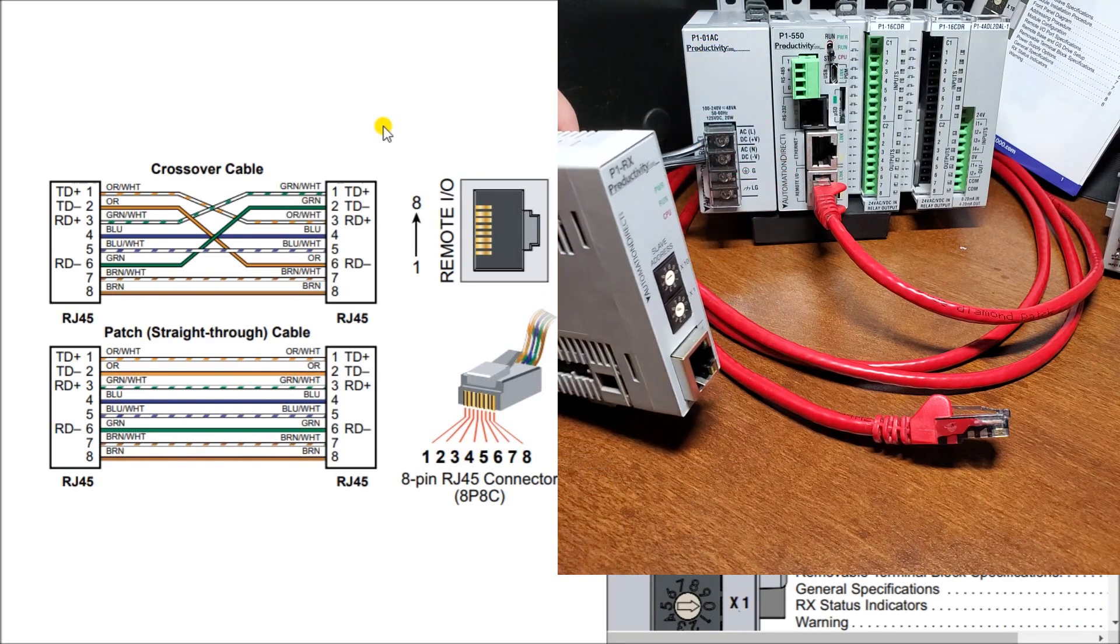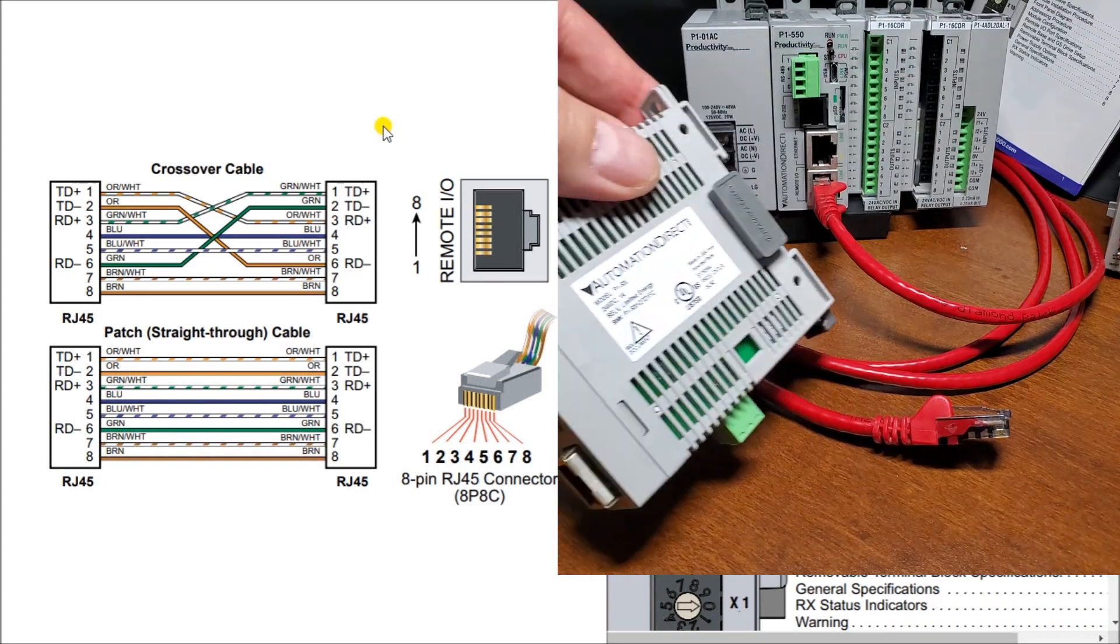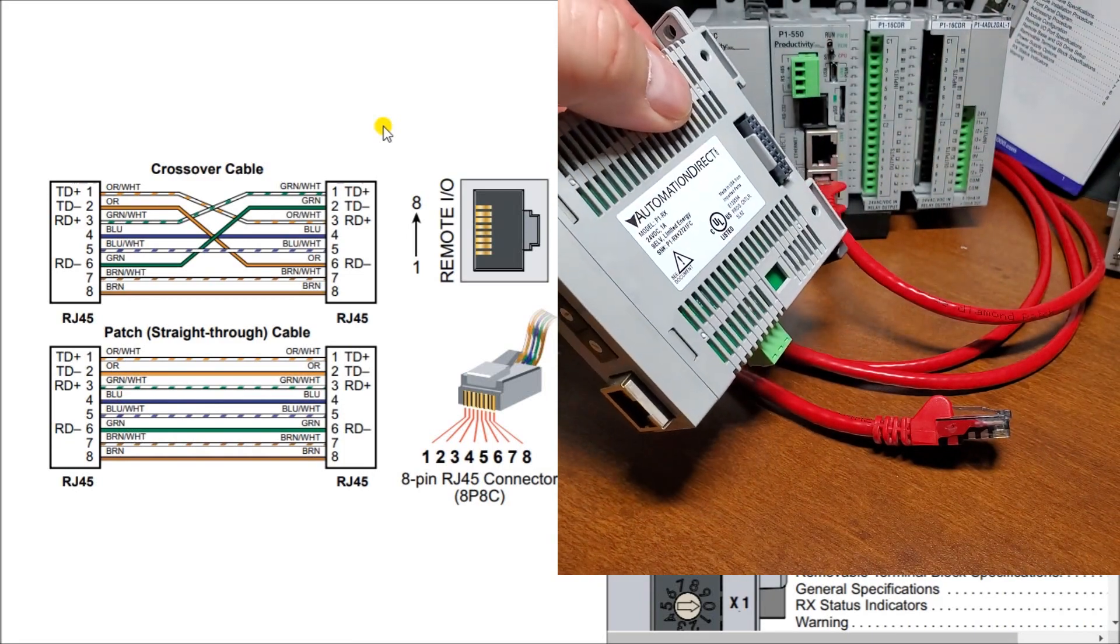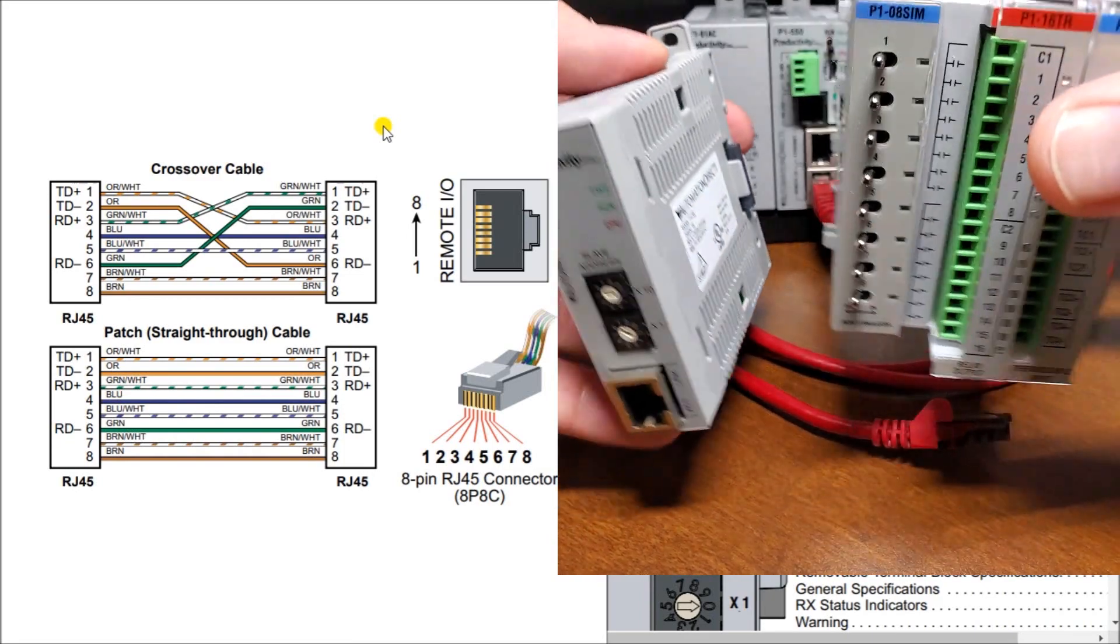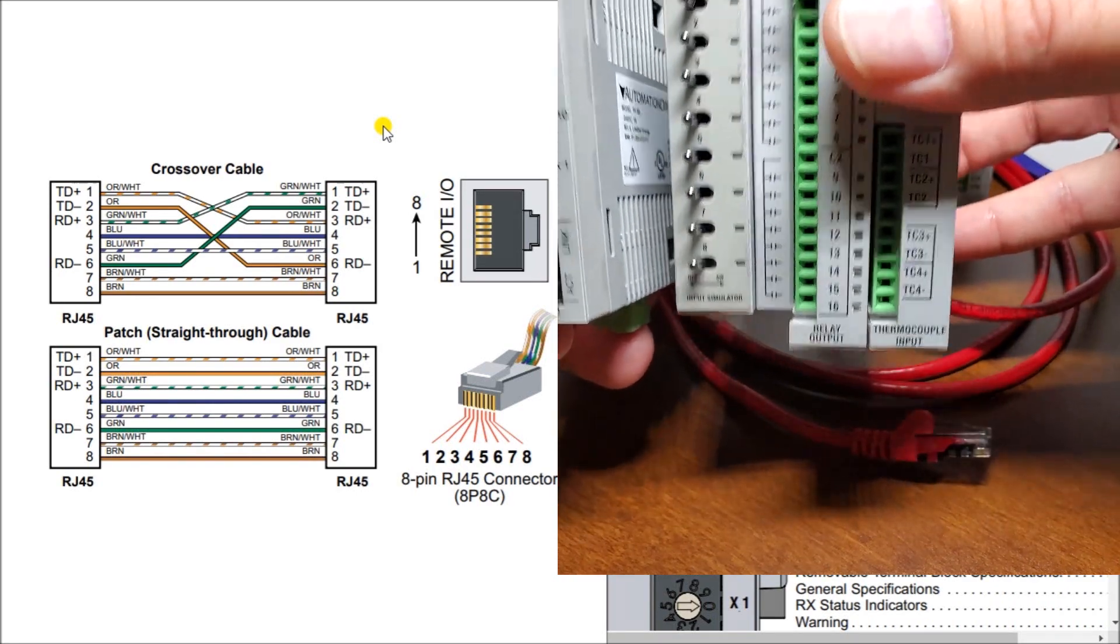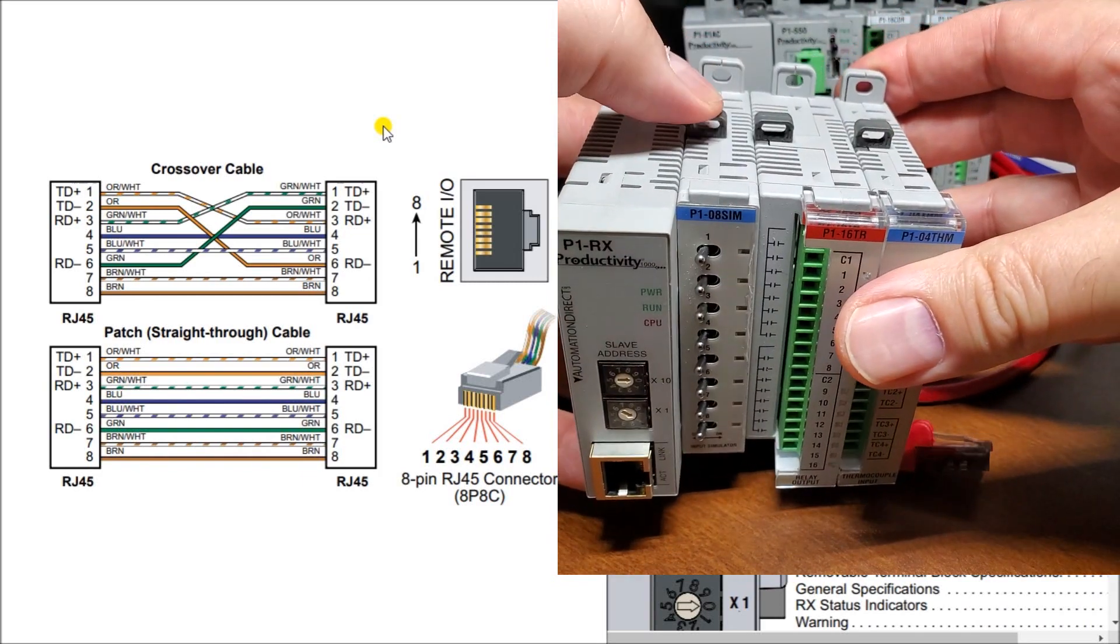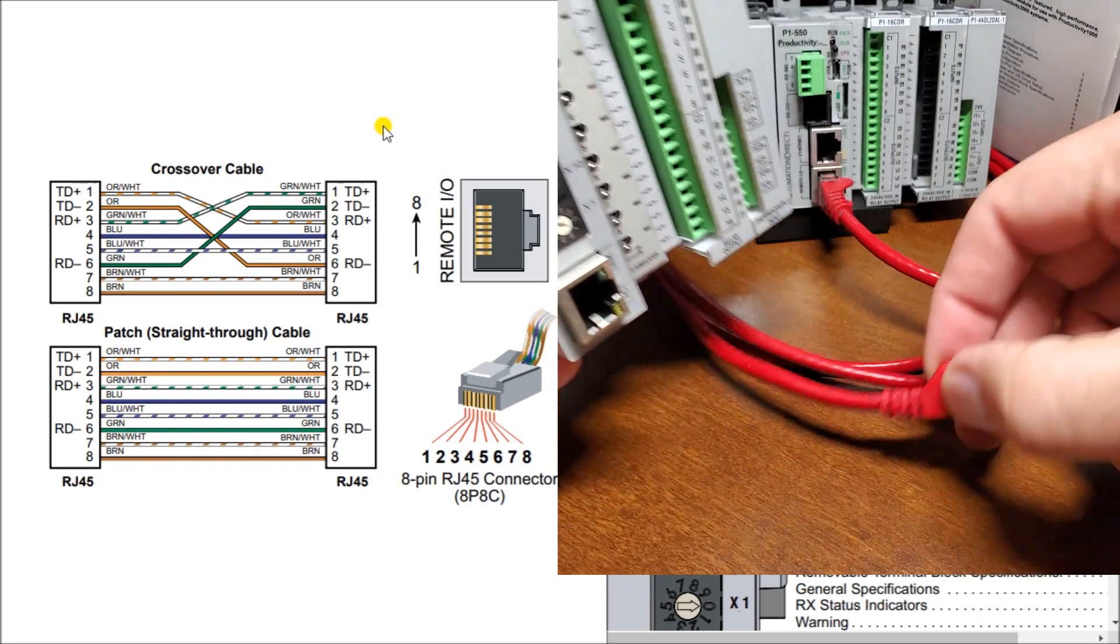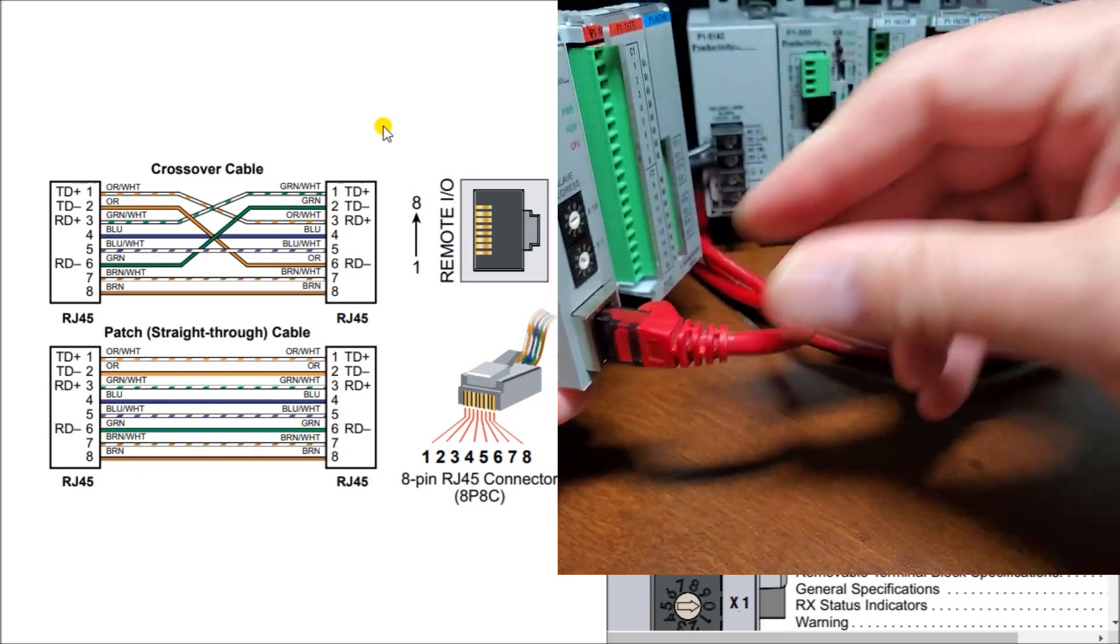So as you notice, like all the P1 series, we have a connector here on our bus. Take that off. We will take our list of I.O. cards that we're going to install, and they will actually snap together to this unit. Press down on the clip, and then it's ready to go. We'll take the bus connector, or the ethernet connection, and we'll just plug that in. So now we have our complete system.